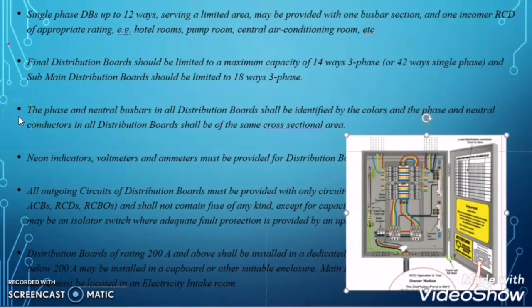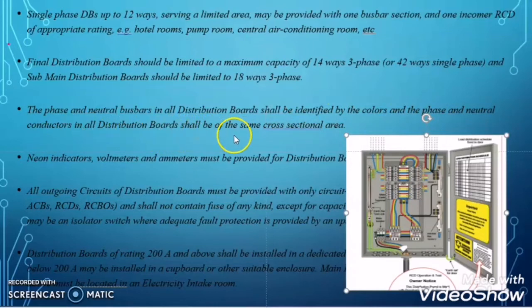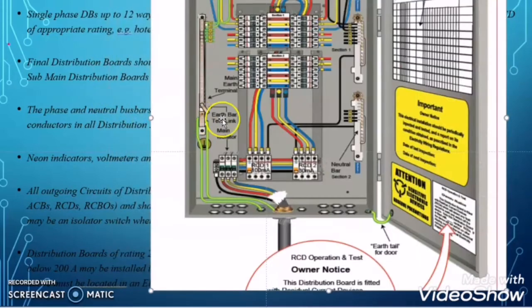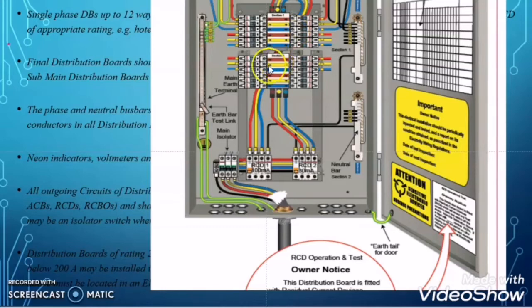The next ADDC clause states that the phase and neutral bus bars in all distribution boards shall be identified by color — R phase by red, Y phase by yellow, and B phase by blue. The cross-section area of the neutral bus bar should be the same as the cross-section area of the phase bus bar. Additionally, neon indicators, voltmeters, and ammeters must be provided for distribution boards rated at 400 amperes and above.